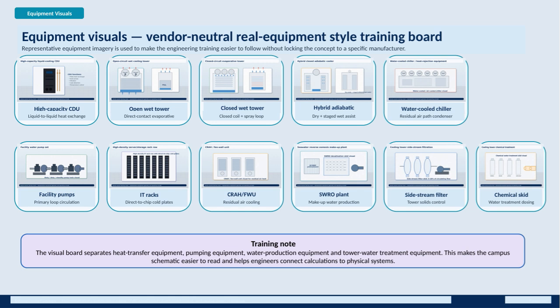The equipment visuals are categorized to clarify their functions and relationships within the system. We highlight various pieces of equipment, such as high-capacity chilled water distribution units, liquid-to-liquid heat exchangers, different types of cooling towers, including open wet, direct contact evaporative, closed wet tower with closed coil plus spray loop, and hybrid adiabatic cooling systems with dry and staged wet assist. Additionally, the visuals include water-cooled chillers, residual air path condensers, facility pumps for primary loop circulation, IT racks with direct-to-chip cold plates, and CRAH or fan wall units handling residual air cooling.